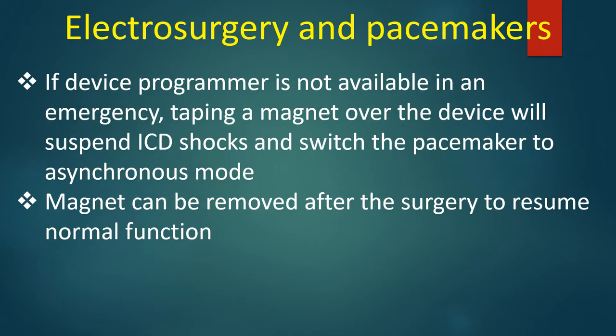If a device programmer is not available in an emergency, taping a magnet over the device will suspend ICD shocks and switch the pacemaker to asynchronous mode. The magnet can be removed after surgery to resume normal function.